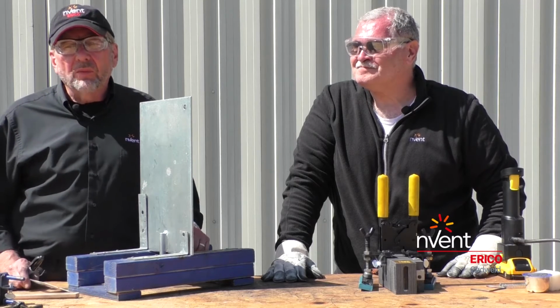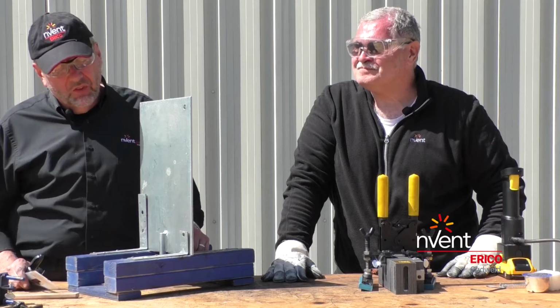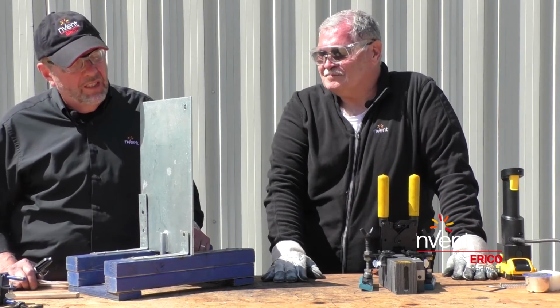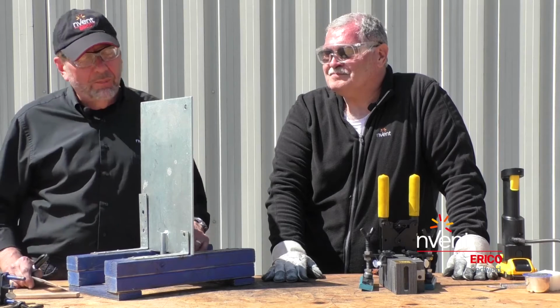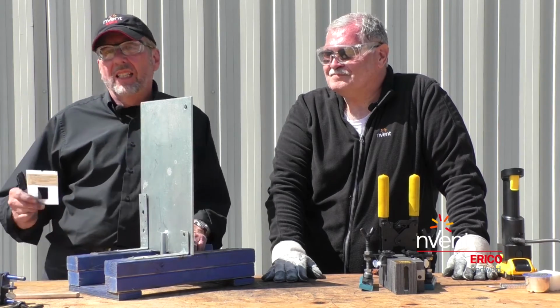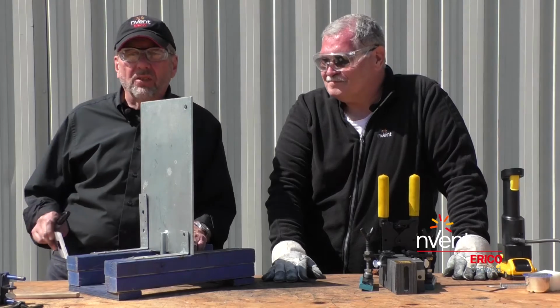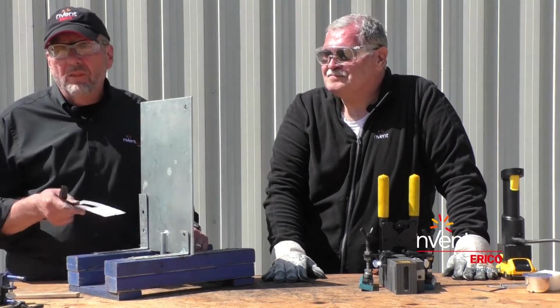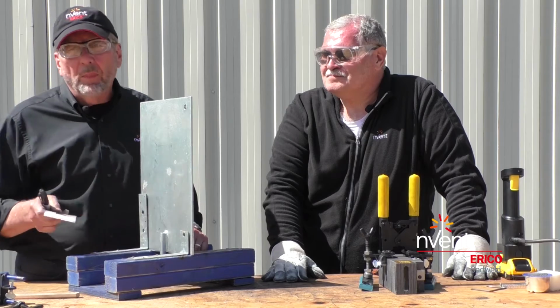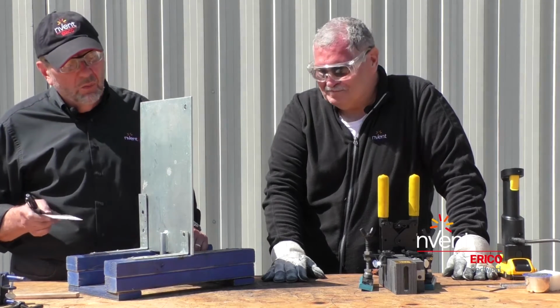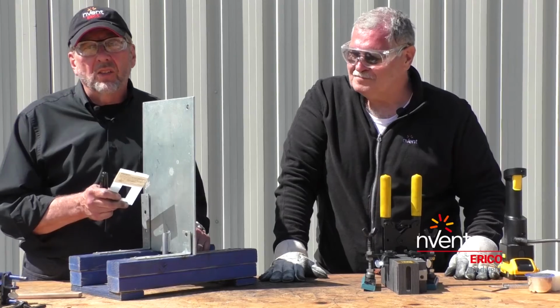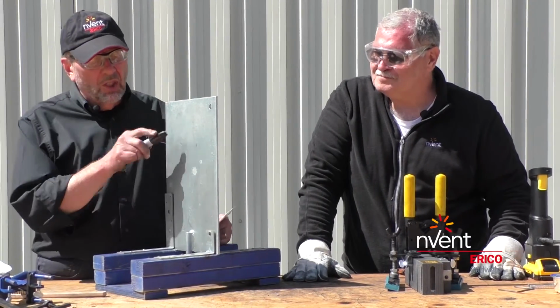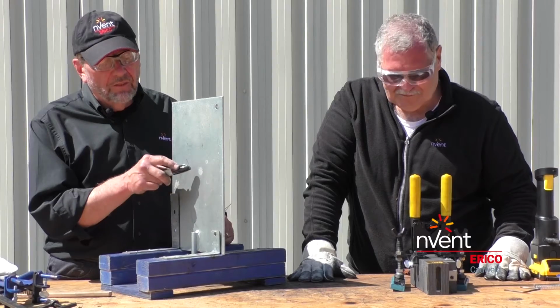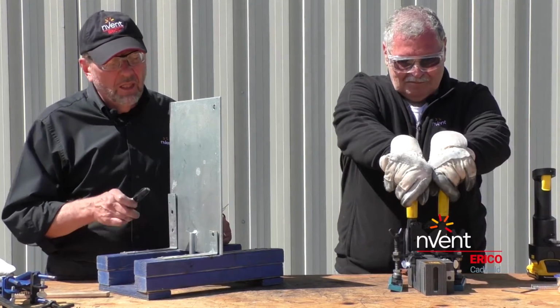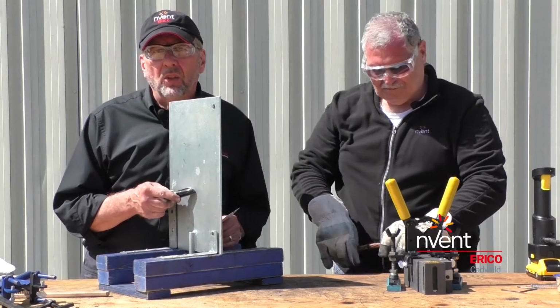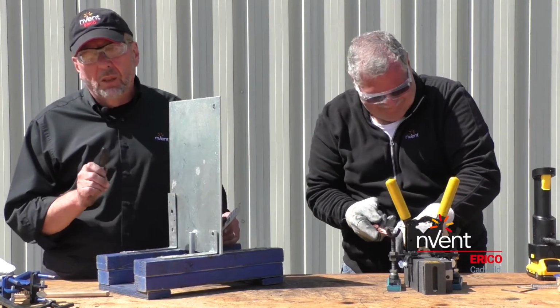The next series of connections we're going to do are cable to a steel surface. Here's our little rig we've set up - this nice piece of galvanized steel stands in for a steel beam or structure in a building, could be a substantial I-beam or part of a structure in a substation. We're going to make a VB connection to this steel surface where the cable will go down off the surface parallel to it - a great connection to use where you don't want a trip hazard.